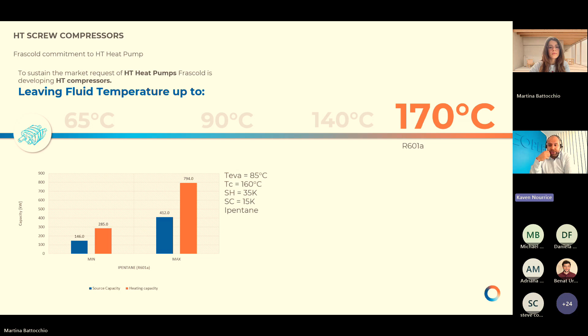The second step is to produce water, and this is the most challenging, up to pressurized water or steam or whatever fluid you need heated up to 170 degrees. For this range of temperature, the best candidate is hydrocarbons, isopentane or pentane. In this case, the capacity is a little bit lower, but we can produce up to 800 kilowatts of capacity.